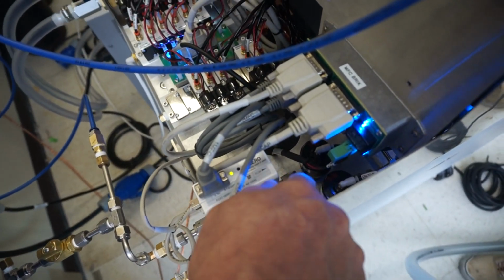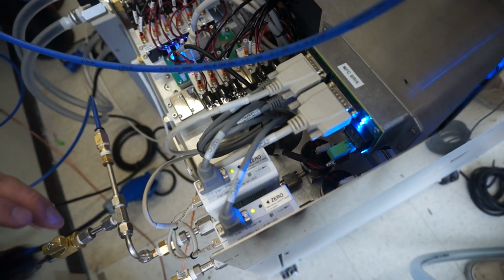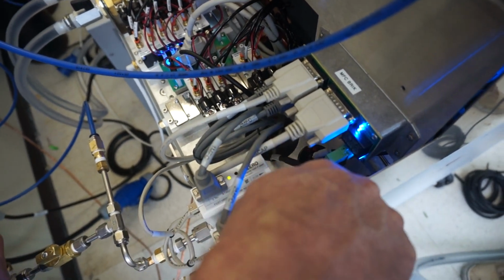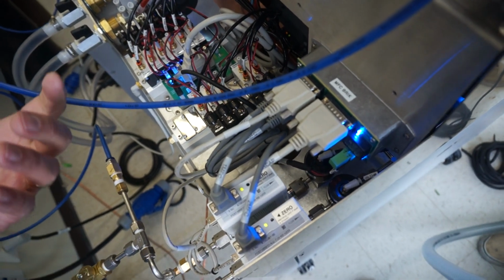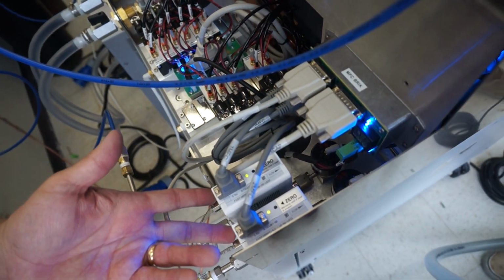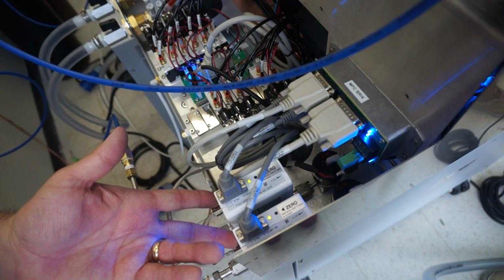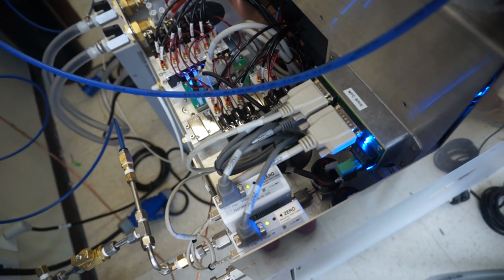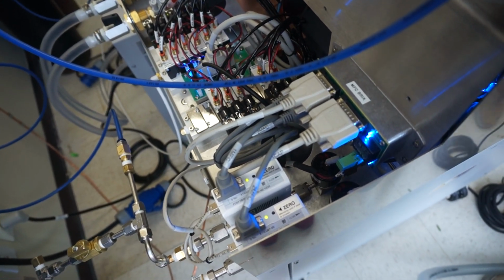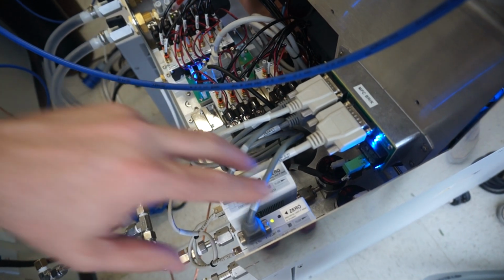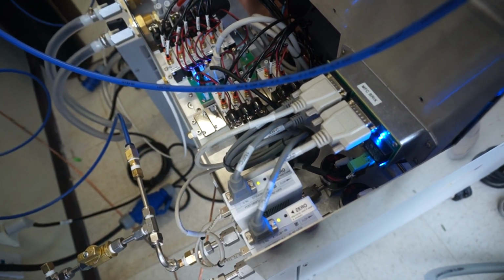So these mass flow controllers, inboard of the mass flow controllers are 2 isolation valves, and they're normally closed valves. Okay. So they're labeled MFC1 and MFC2 ISO. A mass flow controller by design is not a positive shutoff device because of the poppet valve within there. It's not going to positively seal. That's why we have isolation valves upstream of that.